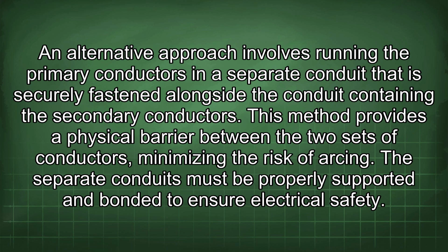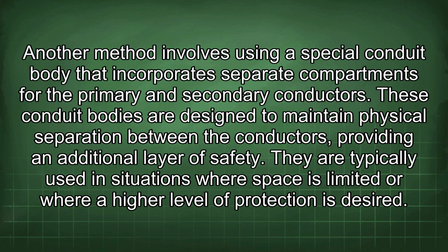This method provides a physical barrier between the two sets of conductors, minimizing the risk of arcing. The separate conduits must be properly supported and bonded to ensure electrical safety. Another method involves using a special conduit body that incorporates separate compartments for the primary and secondary conductors. These conduit bodies are designed to maintain physical separation between the conductors, providing an additional layer of safety. They are typically used in situations where space is limited or where a higher level of protection is desired.